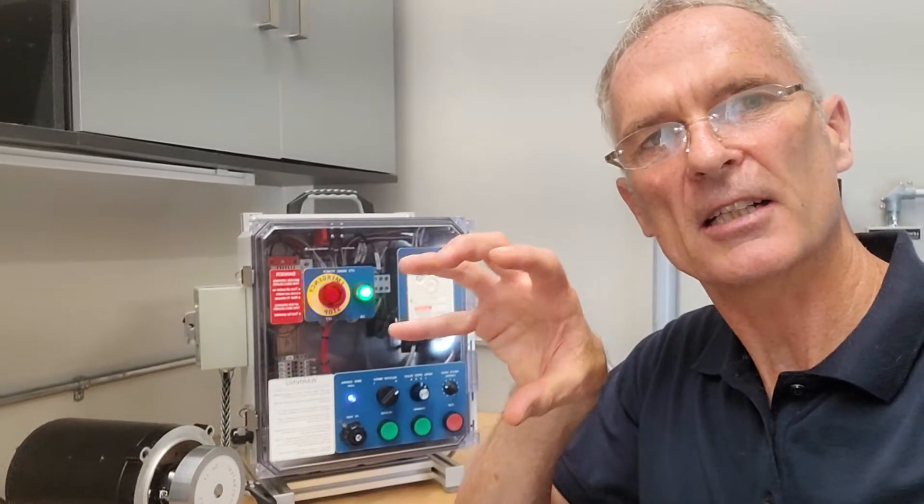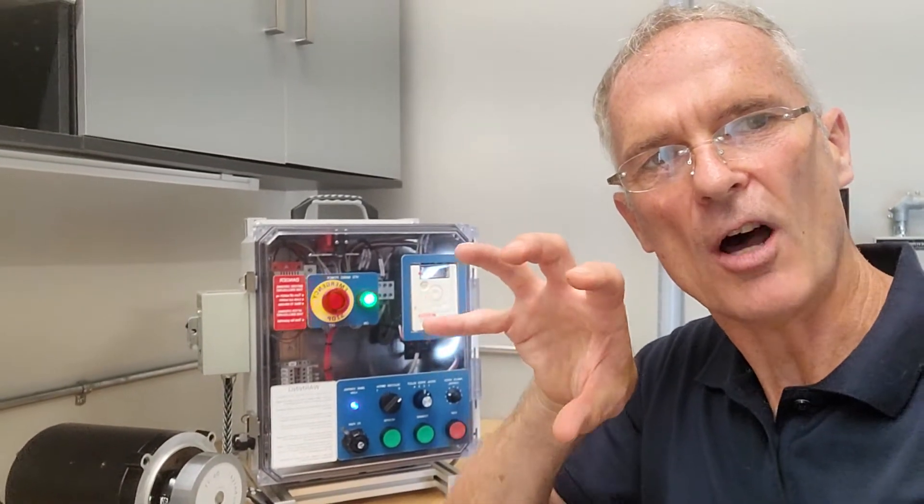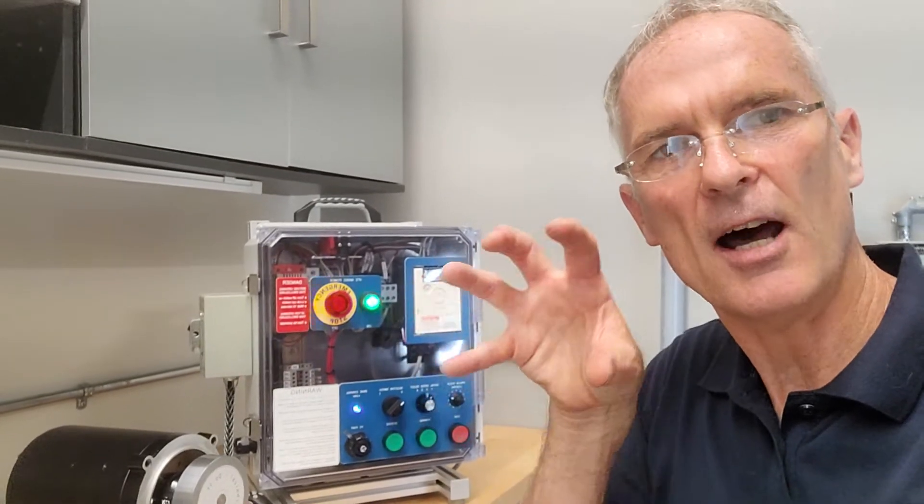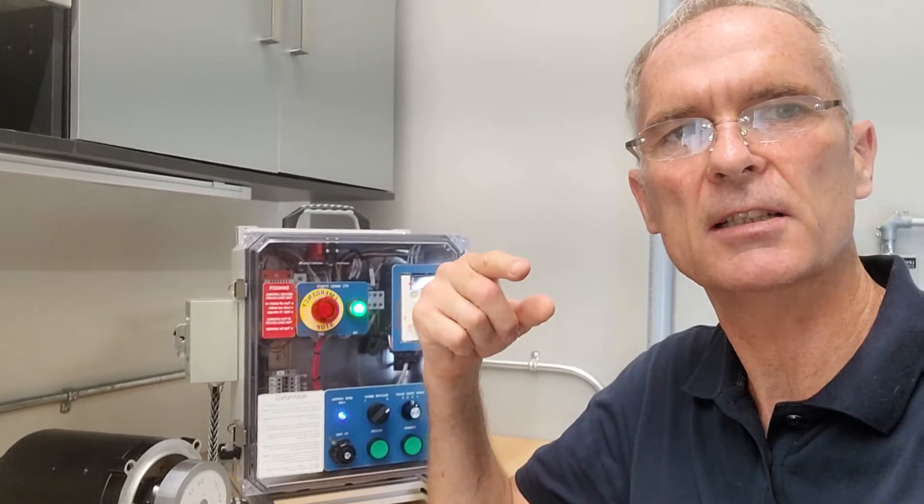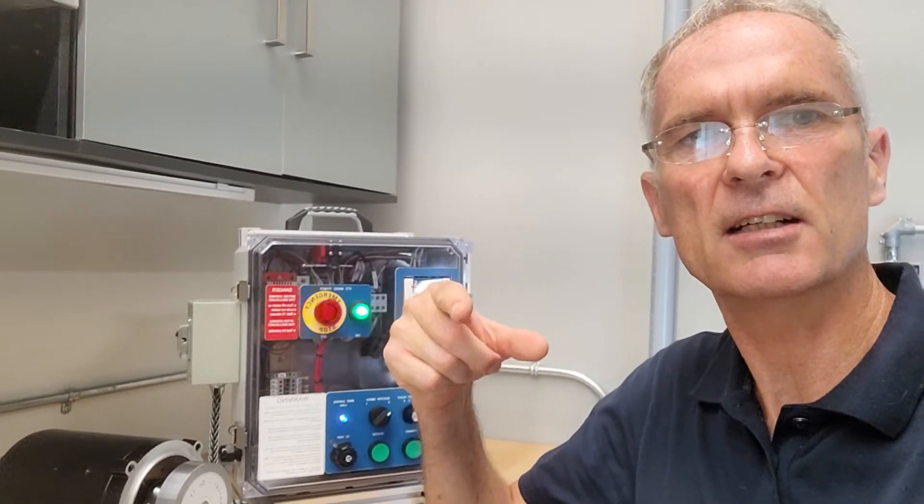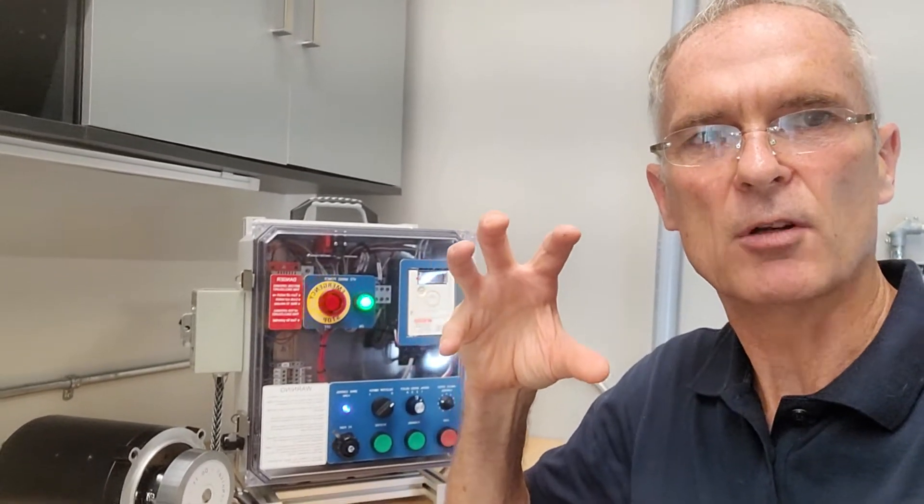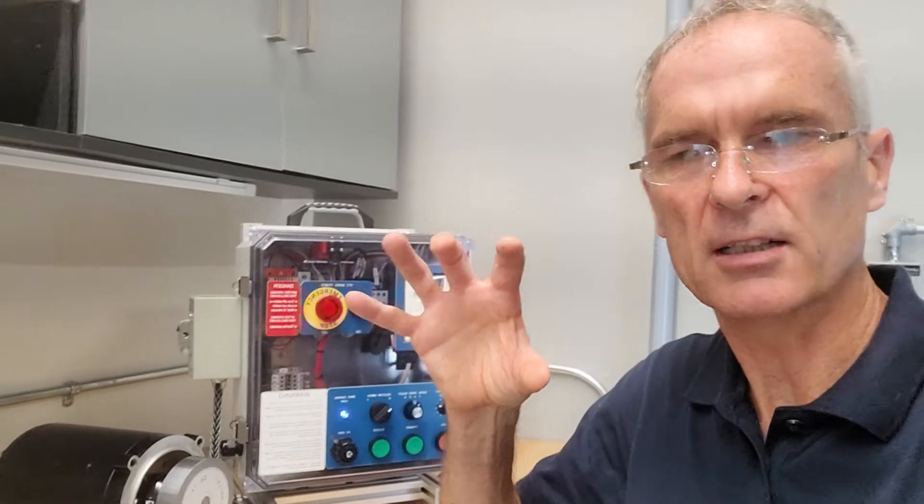The rotor field is opposite to the applied field and it locks up in that field. So if you've got a rotor that's spinning very quickly and you inject DC in there to stop it, it will brake dynamically. It will brake very quickly.